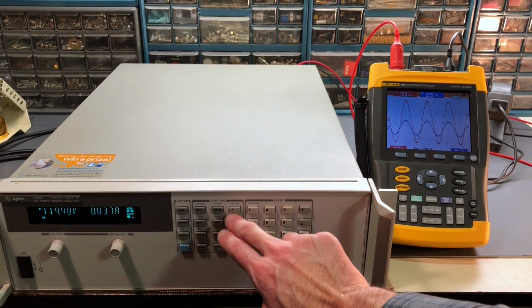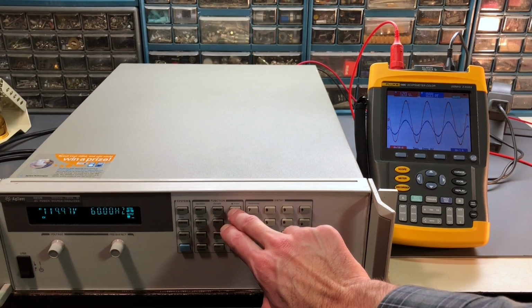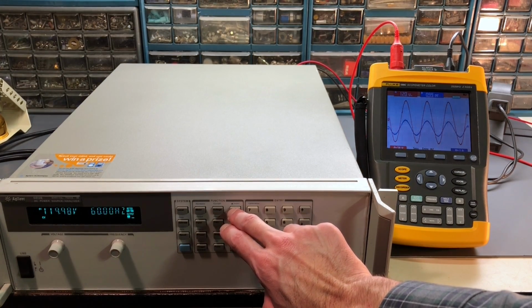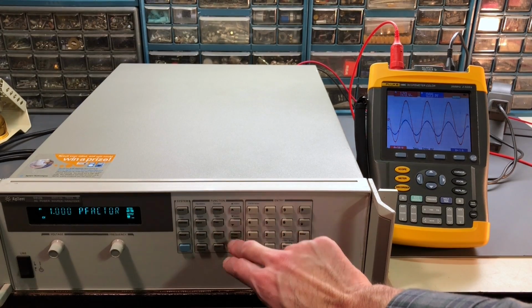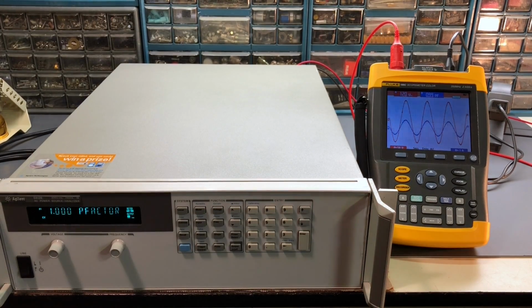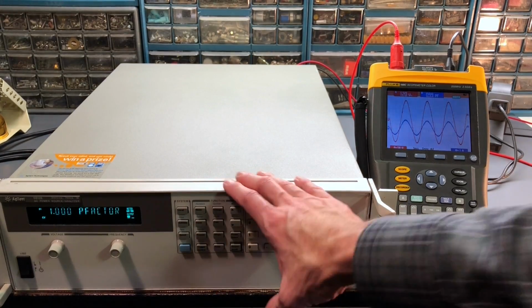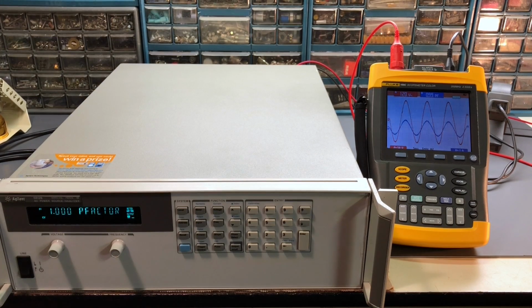volts and amperage, volts and frequency, and back to the power factor again. So all the readings are in agreement with the Fluke Scopemeter. I've gone through everything and everything keeps matching up. So it looks like the calibration on this instrument is really close. I'm not seeing any big discrepancies, so that's nice to see.